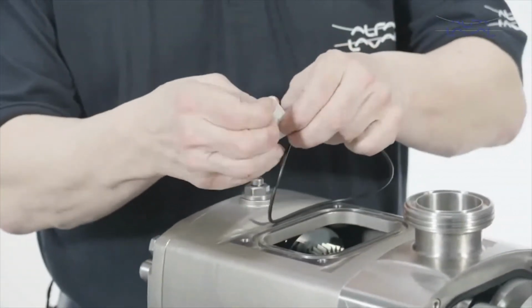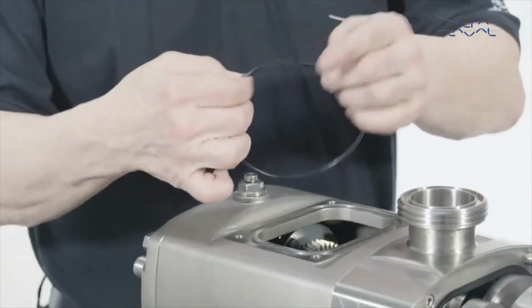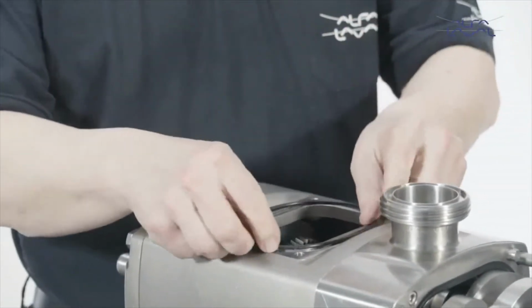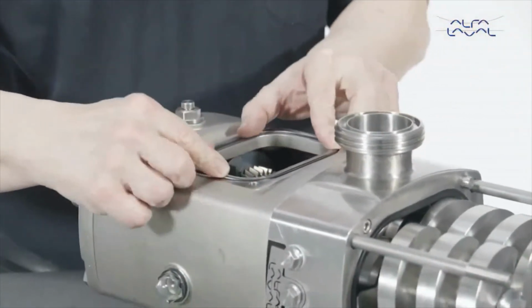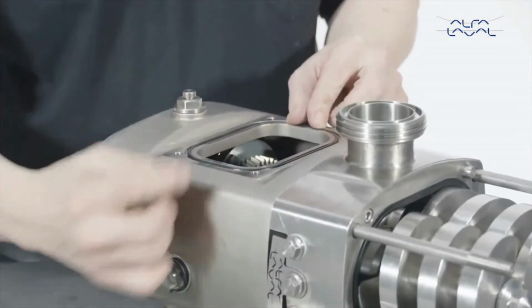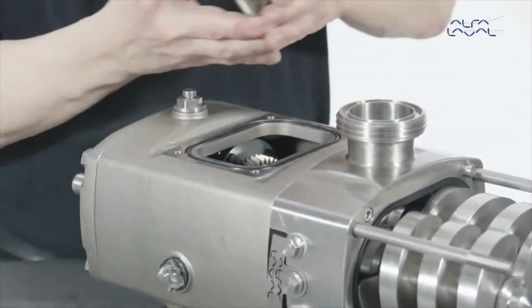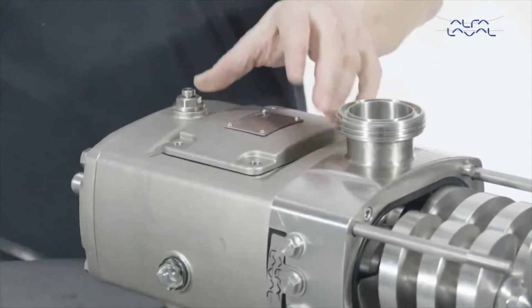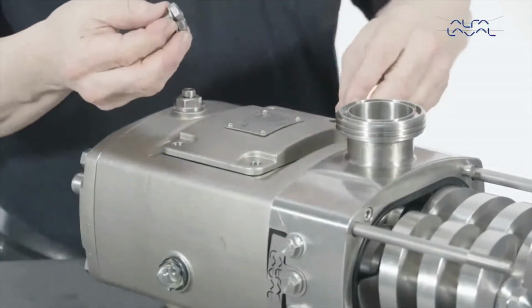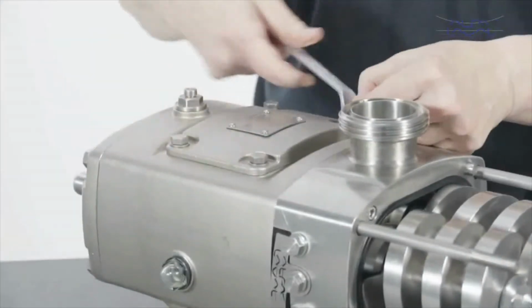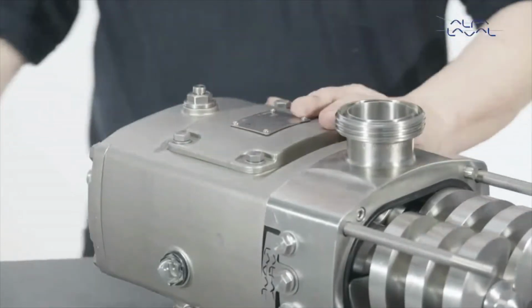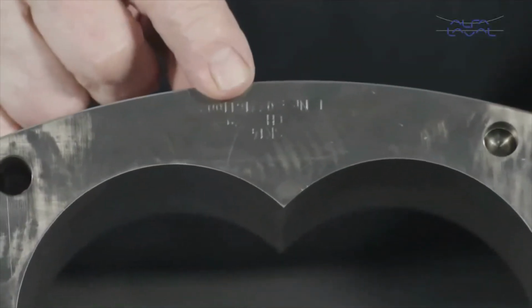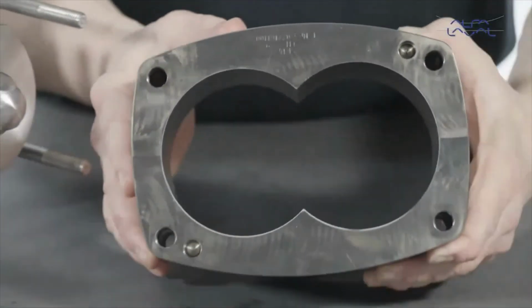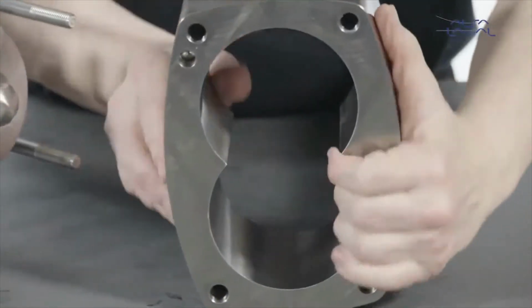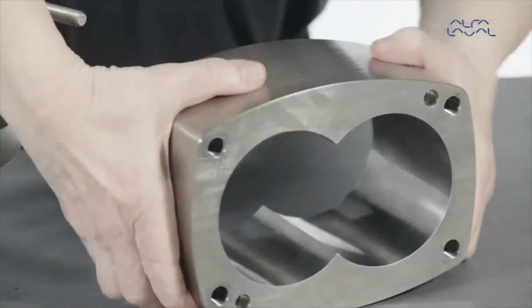Lubricate and replace the gearbox top cover O-ring. Now mount the gearbox top cover. If you drained the gearbox before the maintenance, refill with oil. Fit the pump casing to the new bearing configuration. The pump casing needs to be rotated 180 degrees from its original position.